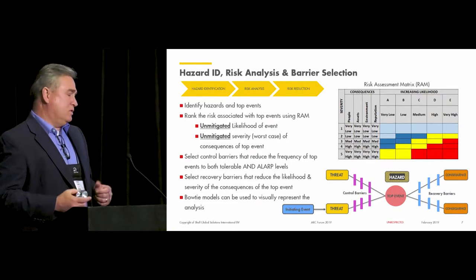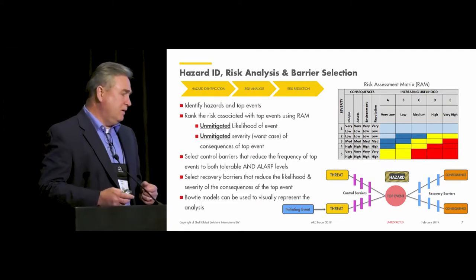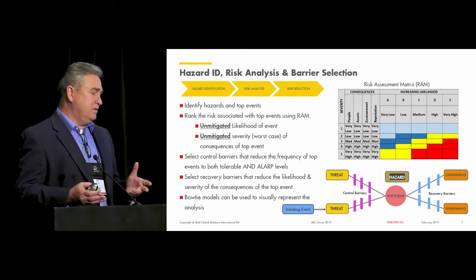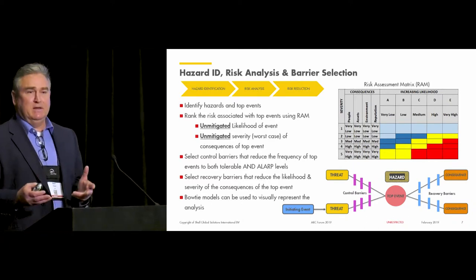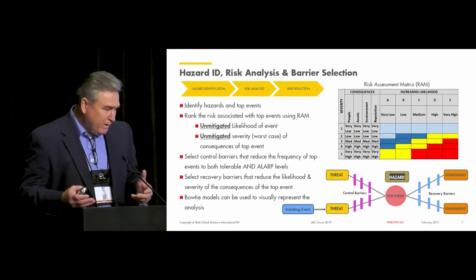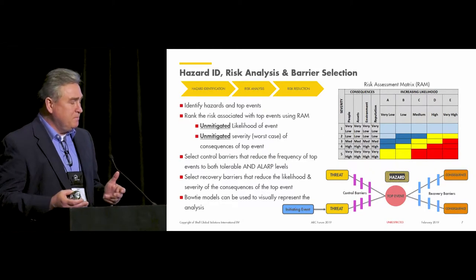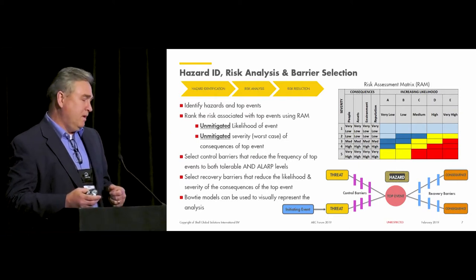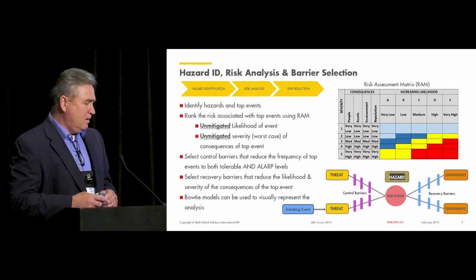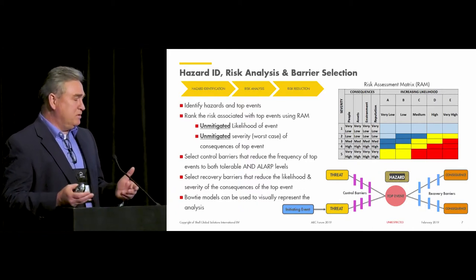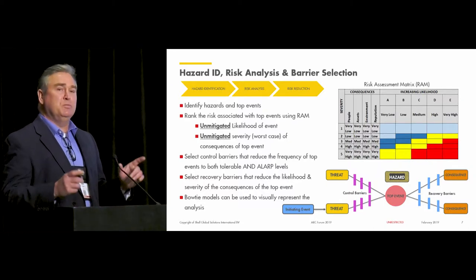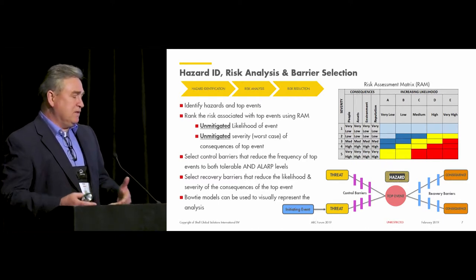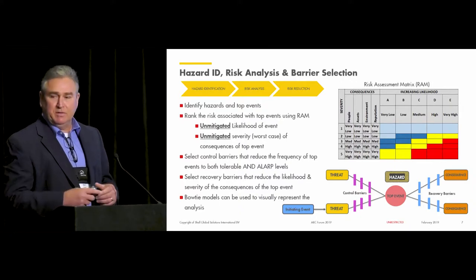This slide squashes three phases into one and introduces a couple of tools. First, identify hazards and top events. Then we use a risk assessment matrix to rank the unmitigated likelihood and unmitigated severity of consequences of the top events — using your company's risk assessment matrix, shown here in a simplified version. The next step is selecting control barriers that reduce the frequency of top events to tolerable and ALARP levels. Then selecting recovery barriers to reduce primarily the severity of top events.